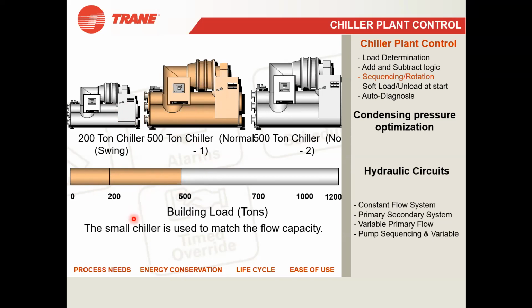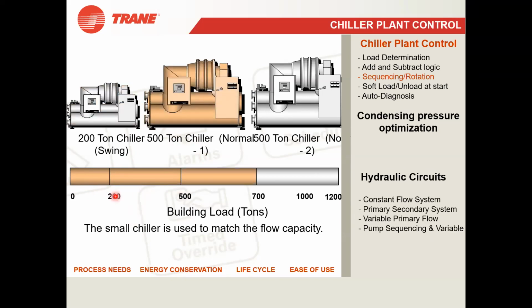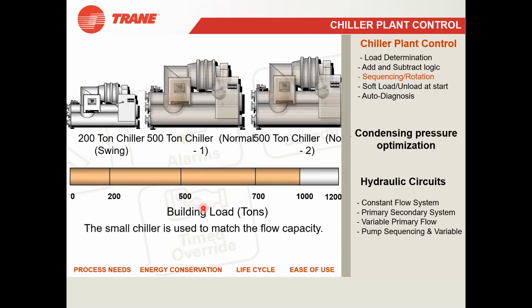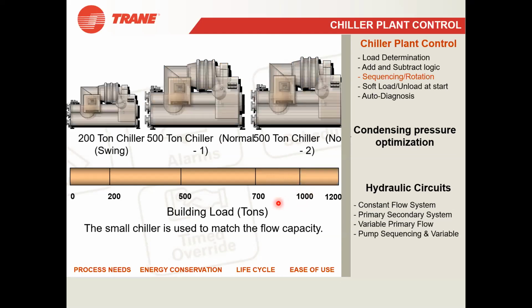After this, if the load is increasing, then again the 200 chiller will be switched on, and until 700 TR these 2 chillers will be working on full load. If the load increases more, the 200 ton chiller will be switched off again, and the 2 500 ton chillers will work together. By using these 2 chillers, it will reach 1000 ton. And after this, if the load is increasing, all the 3 chillers will be switched on, till 1200 ton.